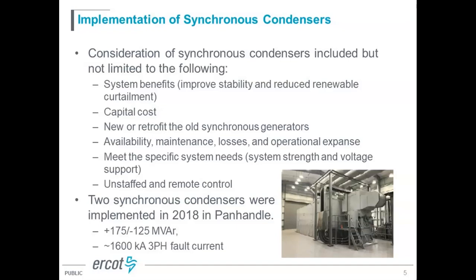So as a result, today we do have two condensers. They were implemented in 2018. These two are almost identical, at two locations inside the panhandle, and the size is around 175 megavars of reactive support. In this case, we did specify a desire to have a higher fault current provided by the condensers in the panhandle to improve the strength and allow the inverters to operate under weaker grid conditions.